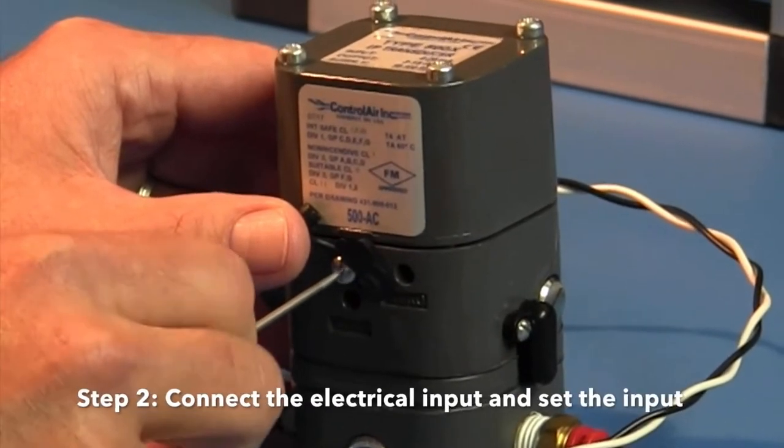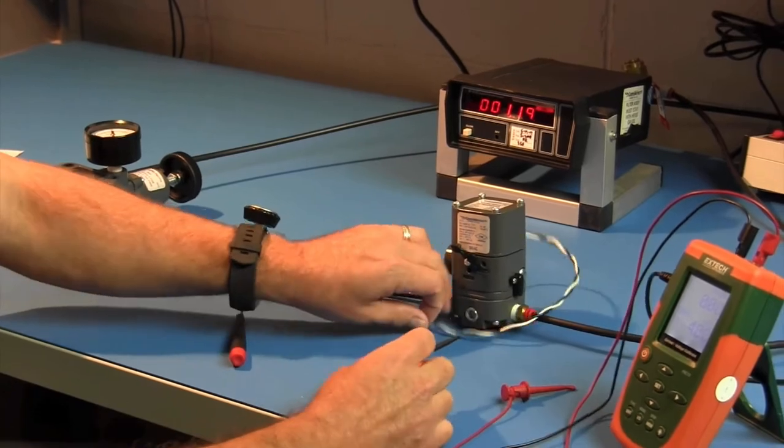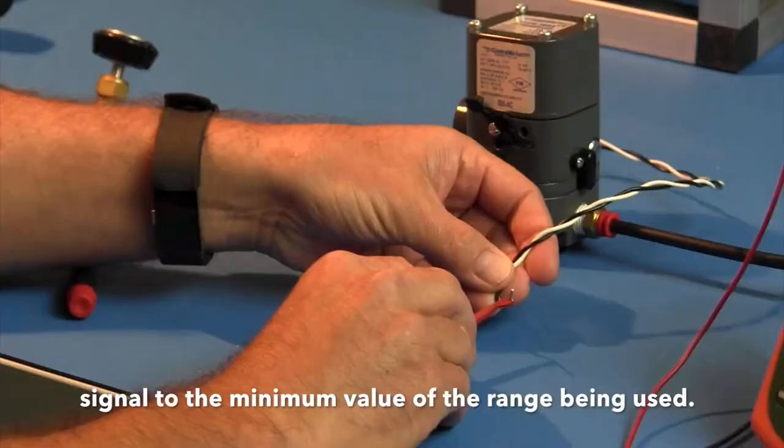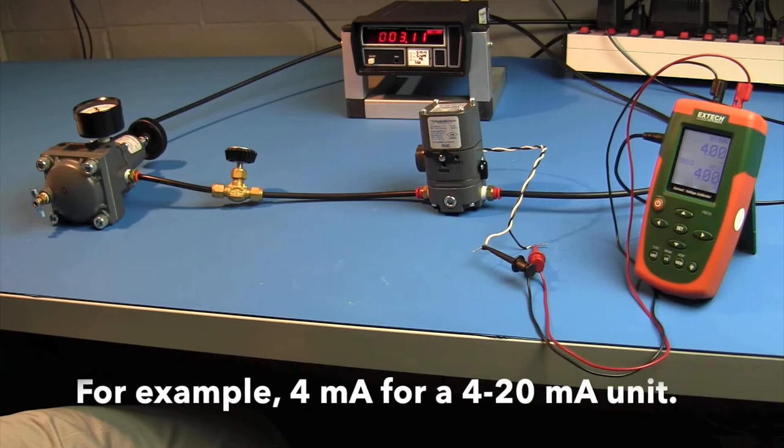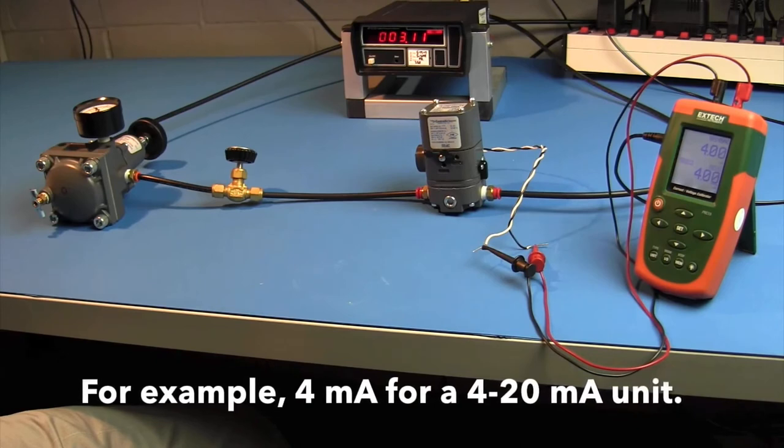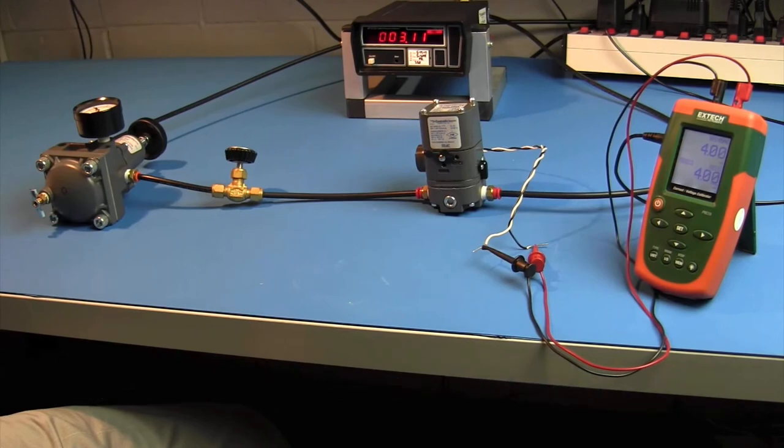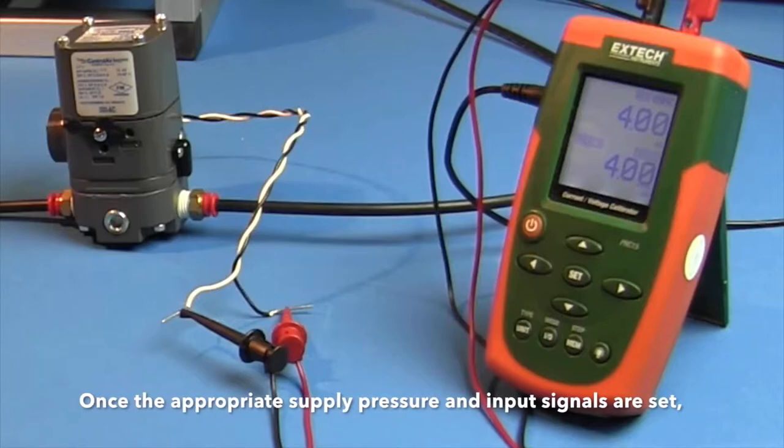Step 2. Connect the electrical input and set the input signal to the minimum value of the range being used. For example, 4 milliamps for a 4 to 20 milliamp unit. Once the appropriate supply pressure and input signals are set, calibration can begin.